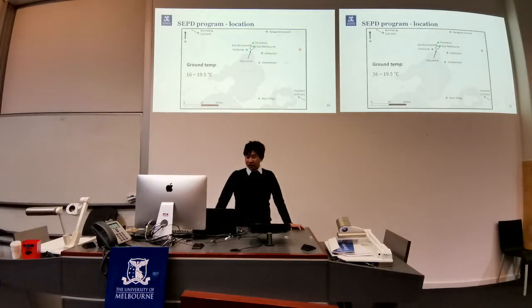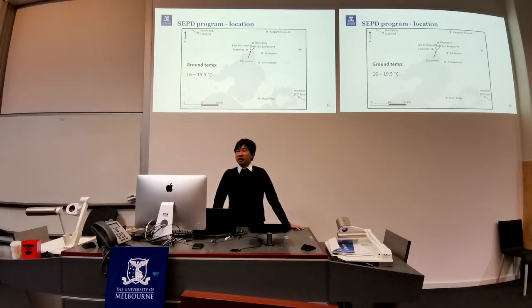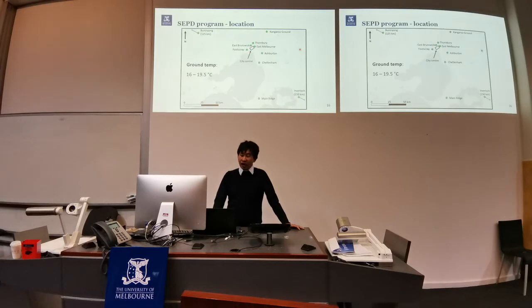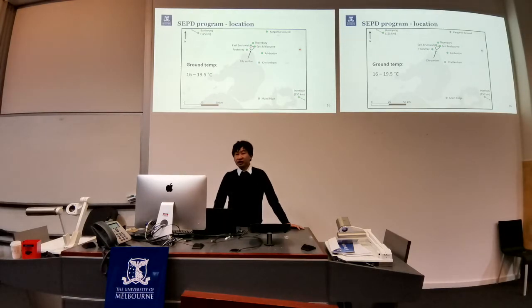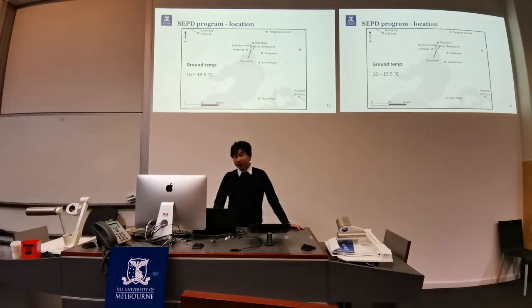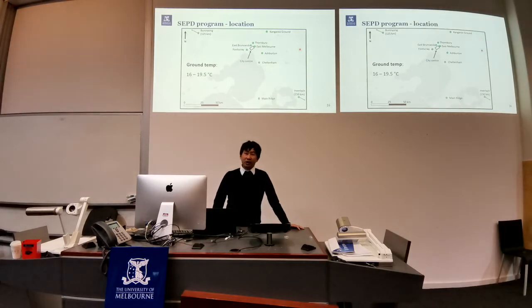One contribution from this project is the monitoring of ground temperature. Our measurement has revealed that the ground temperature can vary from as low as 16 to 19.5 degrees Celsius. This is quite a significant range and quite different from the 18 degrees Celsius that designers typically use for design. If you design with the wrong ground temperature, then it can lead to an inefficient system and high installation costs.